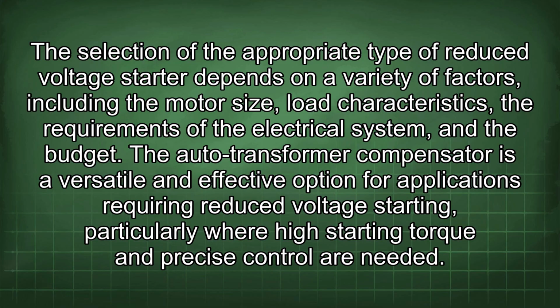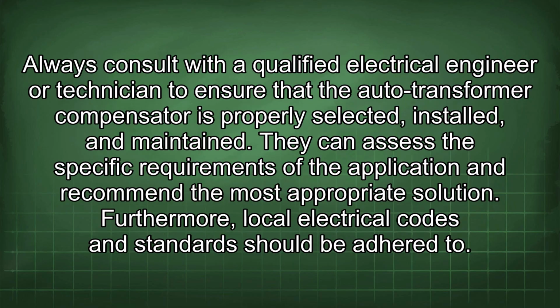The autotransformer compensator is a versatile and effective option for applications requiring reduced voltage starting, particularly where high starting torque and precise control are needed. Always consult with a qualified electrical engineer or technician to ensure that the autotransformer compensator is properly selected, installed, and maintained. They can assess the specific requirements of the application and recommend the most appropriate solution.